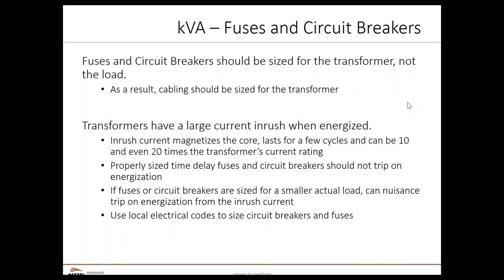Let's briefly touch on inrush current. Inrush current is the maximum instantaneous input current drawn by an electrical device when first turned on. The energization inrush results from the re-application of system voltage to a de-energized transformer. The inrush current can last for a few seconds and can be as high as 15 to 20 times the transformer's current rating. During inrush, the maximum value attained by the flux is over twice the normal flux. Fuses, circuit breakers, and cabling are sized for the transformer, not the load — if sized for the smaller actual load, they can trip on energization from the inrush current.